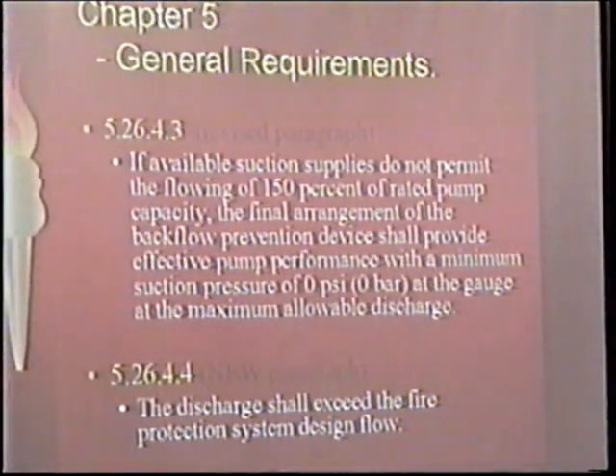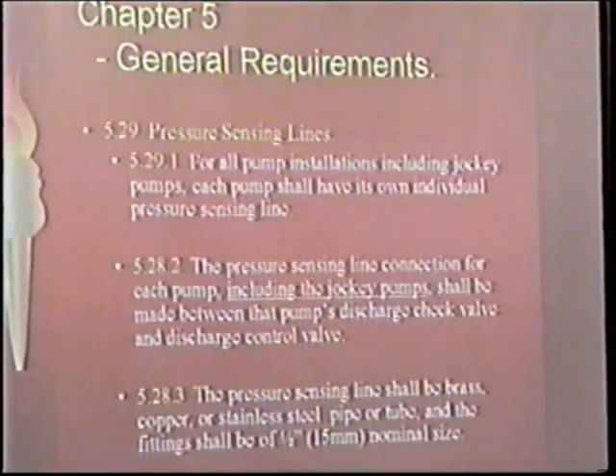It is now. If the city water supply does not allow you to flow 150%, they also qualify that you have to at least flow the system capacity. This was another thing they added. They took this from the annex and put it actually into the code. Is the sensing lines.